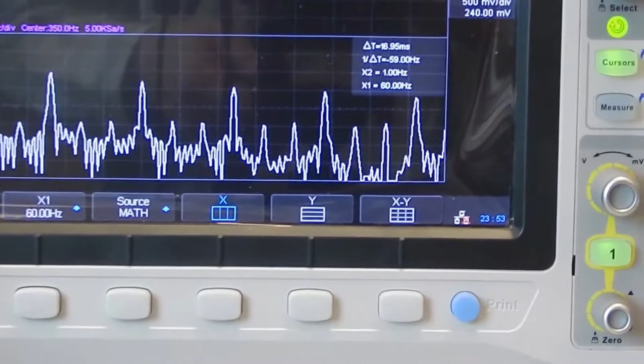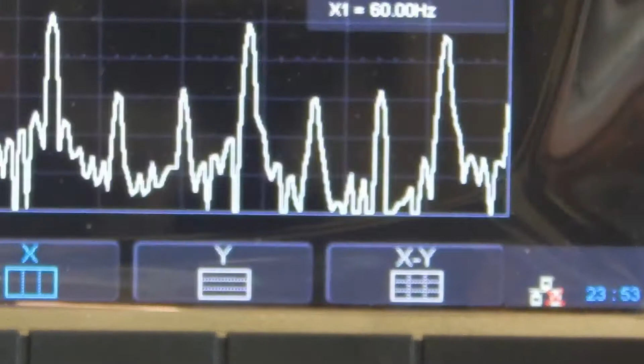Okay, and sure enough, as we move the cursor, we can see it's right on 60 hertz. And if we look at our first harmonic that appears, that should be the third harmonic of 60 hertz. That would be 180 hertz, which is what we get there on the screen. So it's operating just as we expected.